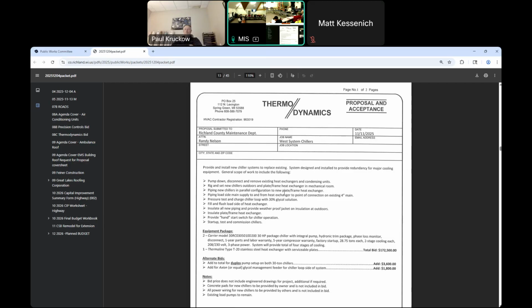Any questions? Will you explain your concern with the two pumps? It sounds like after this is replaced, part of the remaining system might have a failure where we still wouldn't have redundancy. Yeah, and that was one concern I had. It's like I say, we put new chillers in and everything's fine, but you still have three load pumps that pump to the air handlers. If one of those goes down, you are essentially without cooling to that air handler. I didn't see that they were redundant, but they're pretty old pumps.